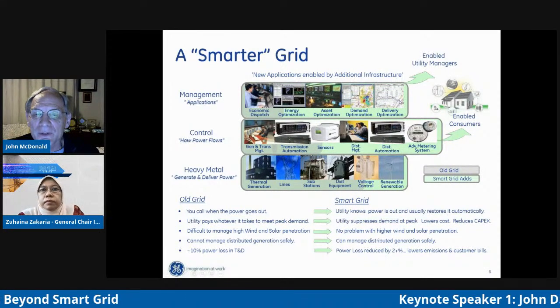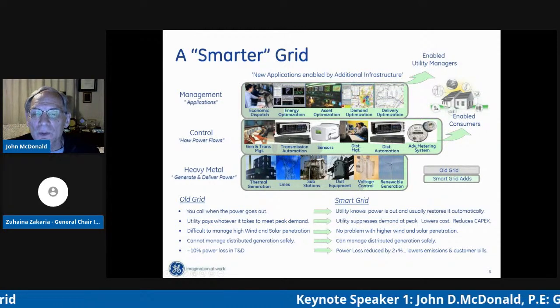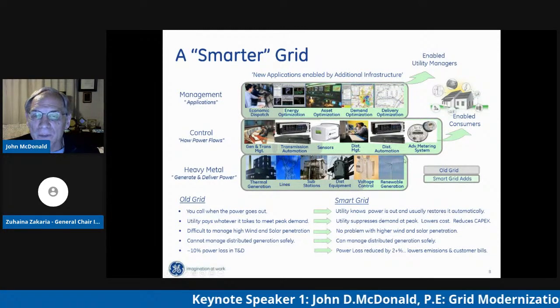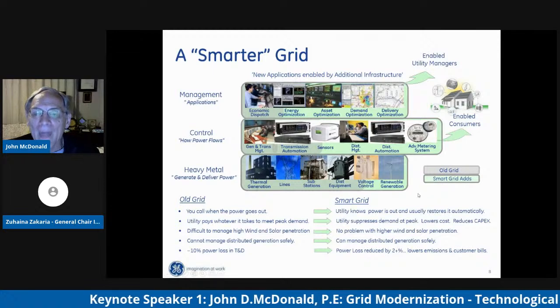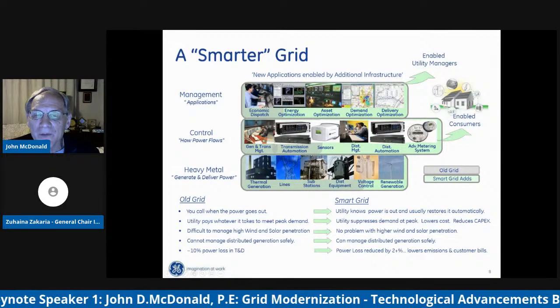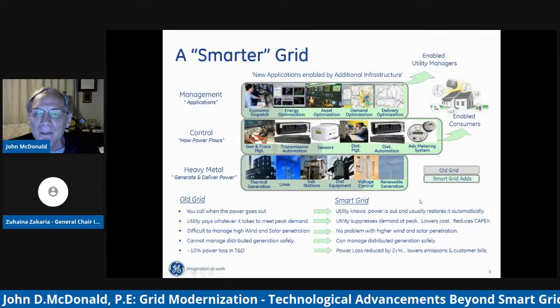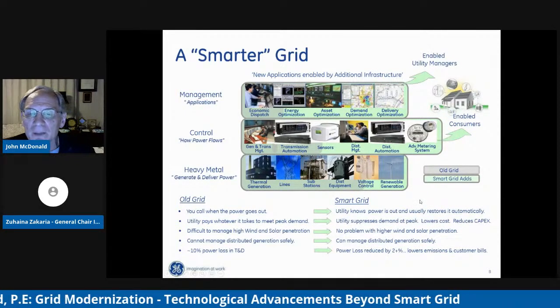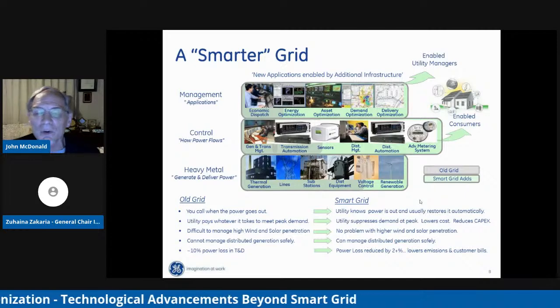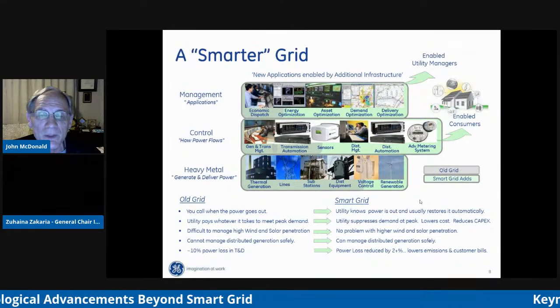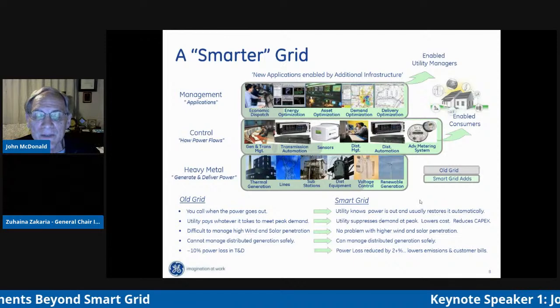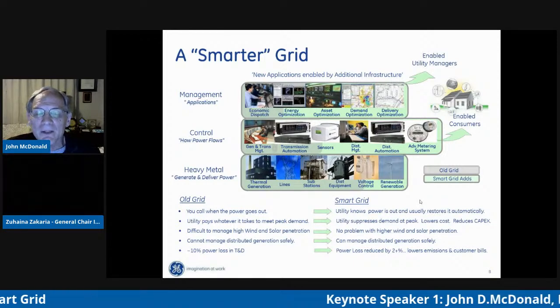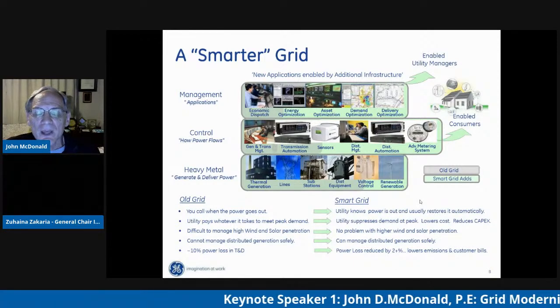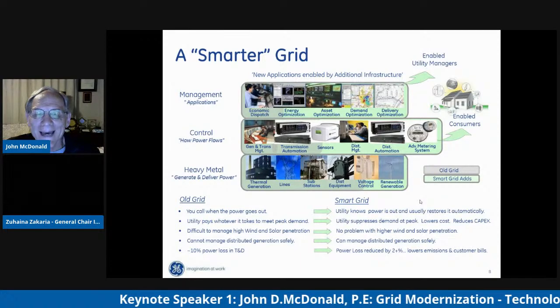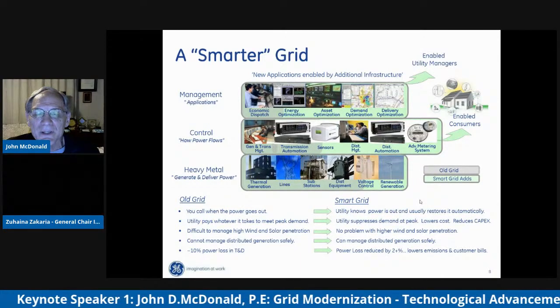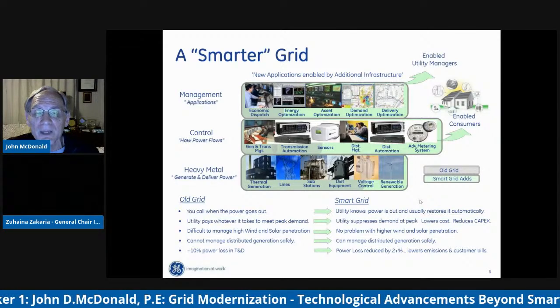For instance, this sensor I show here would be implemented on a transformer, and the oil from the main tank of the transformer would pass through it. This particular sensor can detect up to two gases dissolved in the main tank oil, plus other health data. I could increase that with other sensors to detect up to nine different gases in the main tank simultaneously.